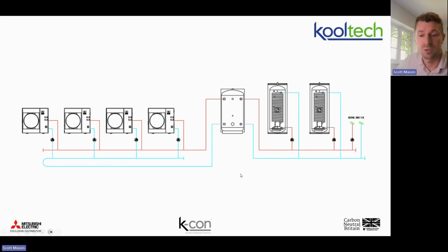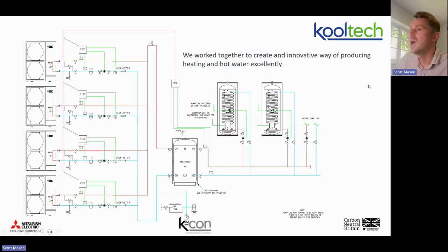But obviously the operational carbon as a result of this goes up slightly, and so does the embodied carbon actually, because these units, although the embodied carbon in transportation is lower and stuff, they're R32, which is about a GWP of 600, whereas the CAHVR is a 454C, so GWP of 148, and the charge volume will be less than 4 of these added together. So again, site-by-site considerations, this is what we're here for to talk about, but that's pretty much what we do.